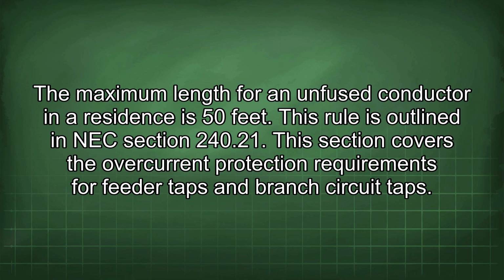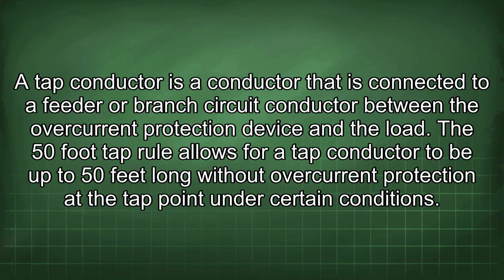This rule is outlined in NEC section 240.21. This section covers the overcurrent protection requirements for feeder taps and branch circuit taps. A tap conductor is a conductor that is connected to a feeder or branch circuit conductor between the overcurrent protection device and the load. The 50-foot tap rule allows for a tap conductor to be up to 50 feet long without overcurrent protection at the tap point under certain conditions.